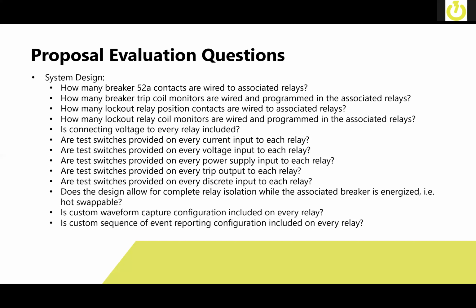A lot of times, some of these facilities run 24/7 and they don't want to take the time to take an outage just to test this equipment. If you do the test switch design right, a lot of times it is possible to still perform maintenance while keeping that equipment running with minimal risk. And then from an event analysis standpoint, is custom waveform capture configuration included? Is custom sequence of event reporting configuration included on all the relays? A lot of times what we'll see is the relay manufacturers have an out-of-the-box setup that puts in different inputs, different outputs, and some basic signals in those event analysis capabilities.